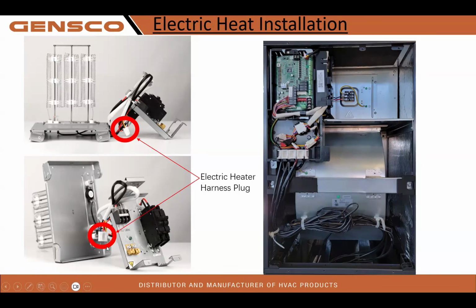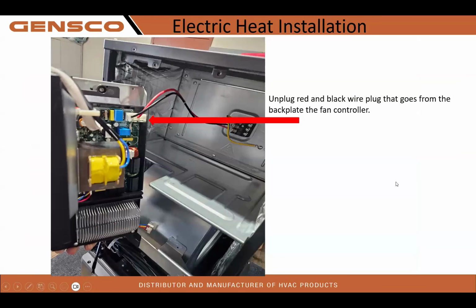Notice our heat kit plugs right here. It is all plug and play. Unplug the wiring harness right here. Let this control board slide out of the way, removing these 3 screws, 1 there, 1 there, 1 there. We will unplug the red and black wire plug that goes from the back plate and the fan control. Notice our flat plug right here ties into S1, S2, line 1, line 2, and ground. Do not throw this plug away. And I'm going to explain why, because we're going to use that as a jumper to power our indoor control board.